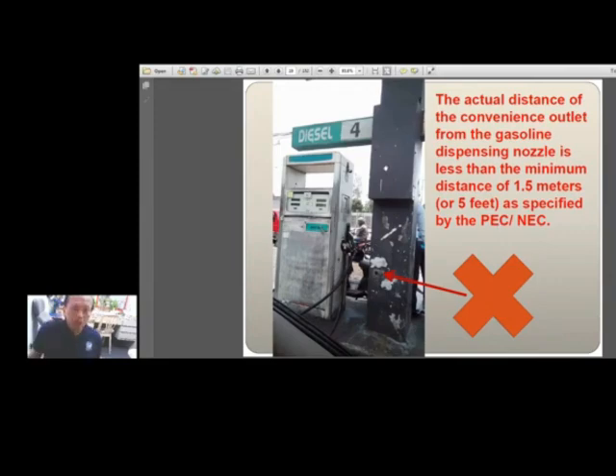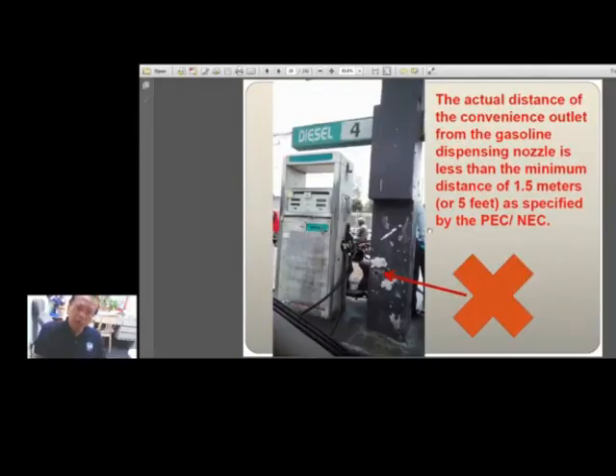If you see, the panel board is here above, and you would see an outlet here below, and therefore it is even closer to the gas dispenser, no? Okay, so it's really a violation of the code. The engineer who signed the plans does not know his code. The one who supervised the project also doesn't know the code, and much more the building official, the inspector who allowed this to be done. So anyway, let's make it a lesson. It should not happen, should not be done again in other parts of the country.